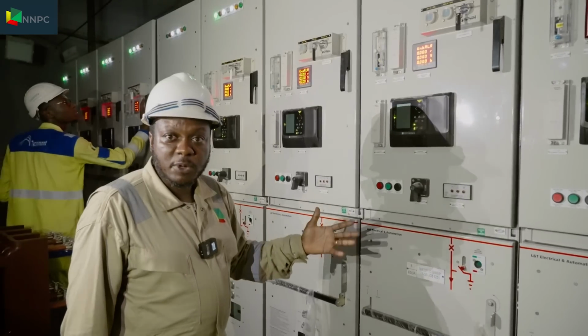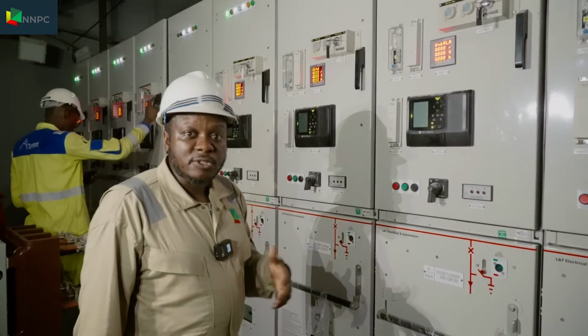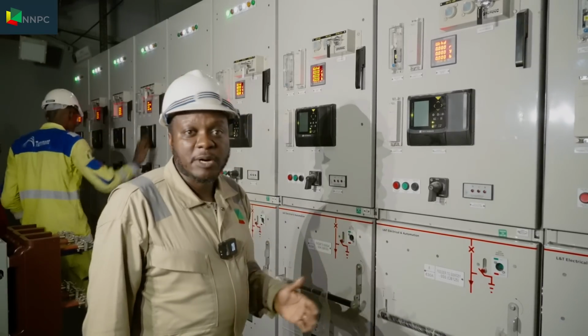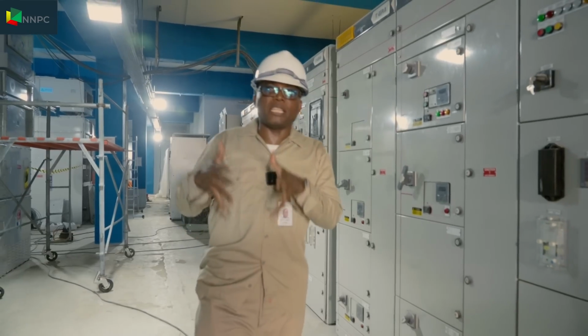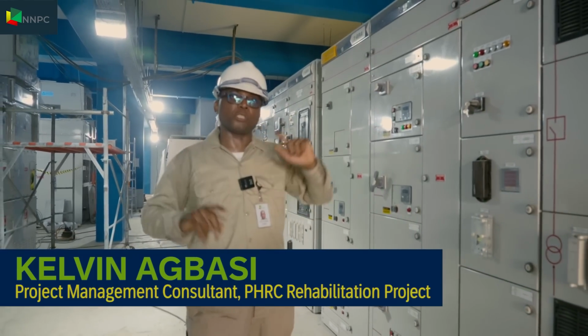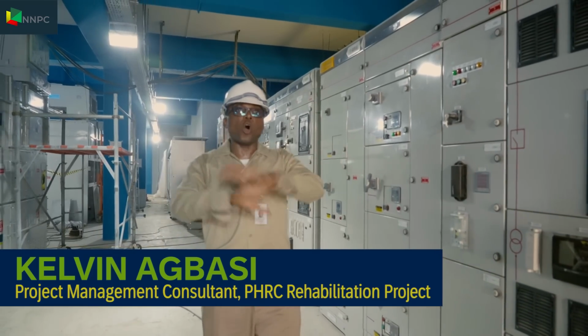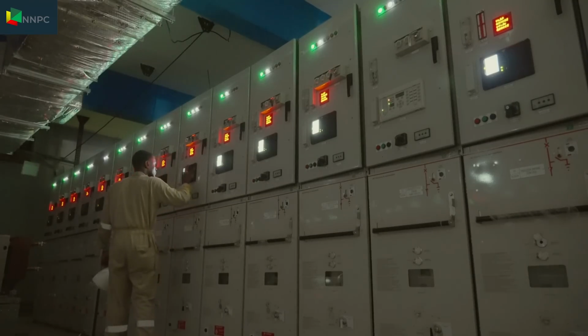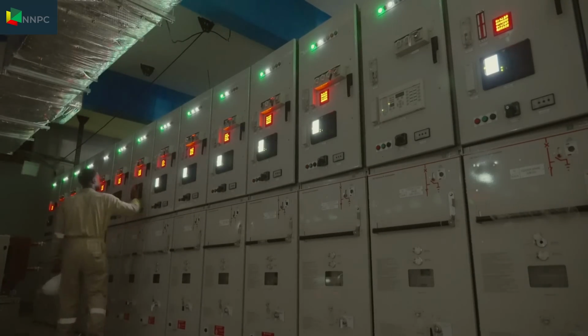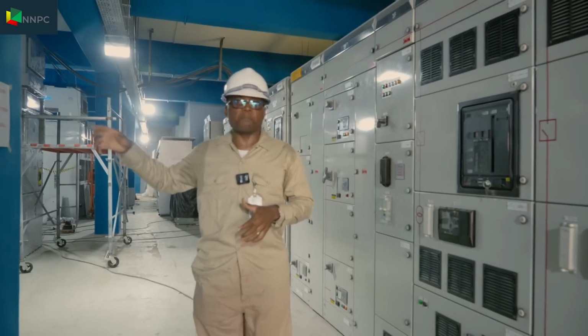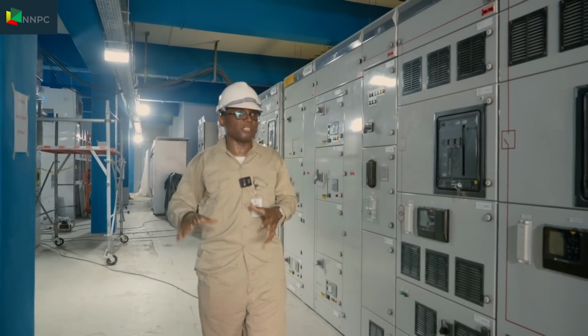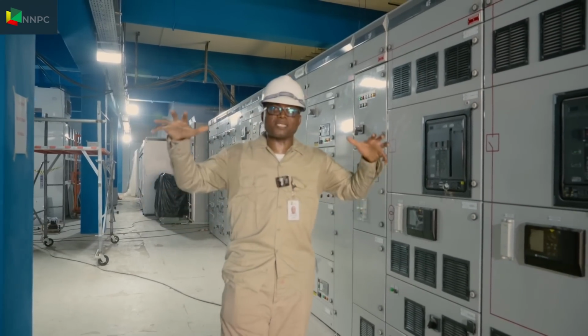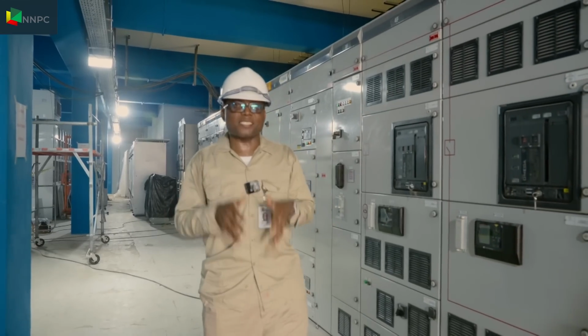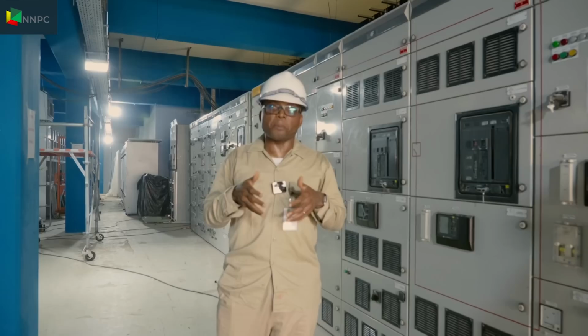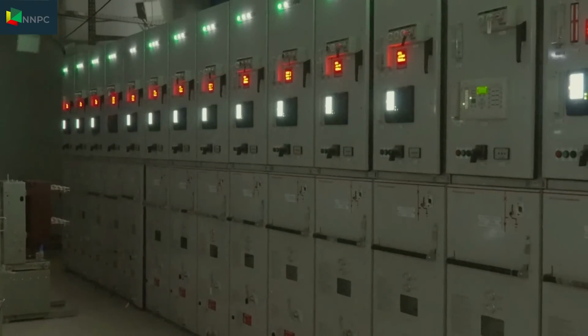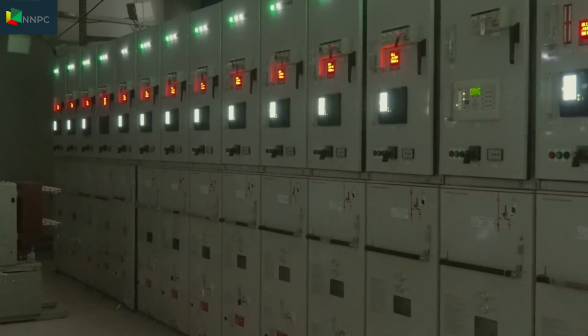Commissioning is ready for sub one. Sub one is commissioned, and we are just doing the final check so that we can send out power to the other substations. Then immediately from sub one, it is transmitted to substation B, which powers all Area 5 substations. And also from here, we power the PPU, we power the life camp, we power the wastewater, and we power the new refinery. So it all indeed starts here. This is the primary substation for the Port Harcourt refinery, both old and new. And from here, power goes everywhere else.